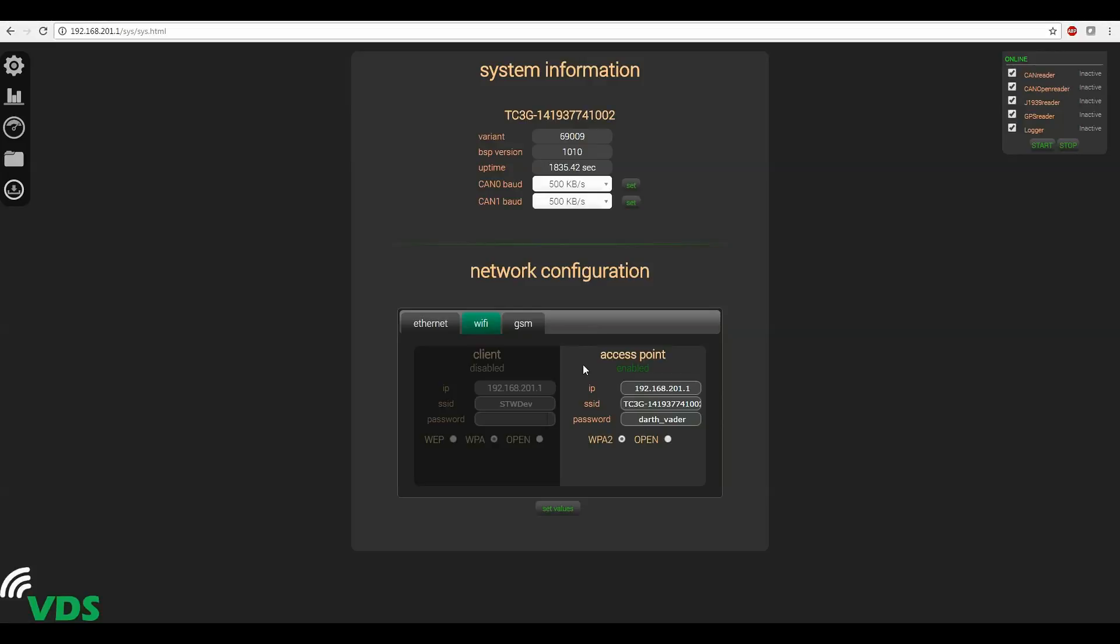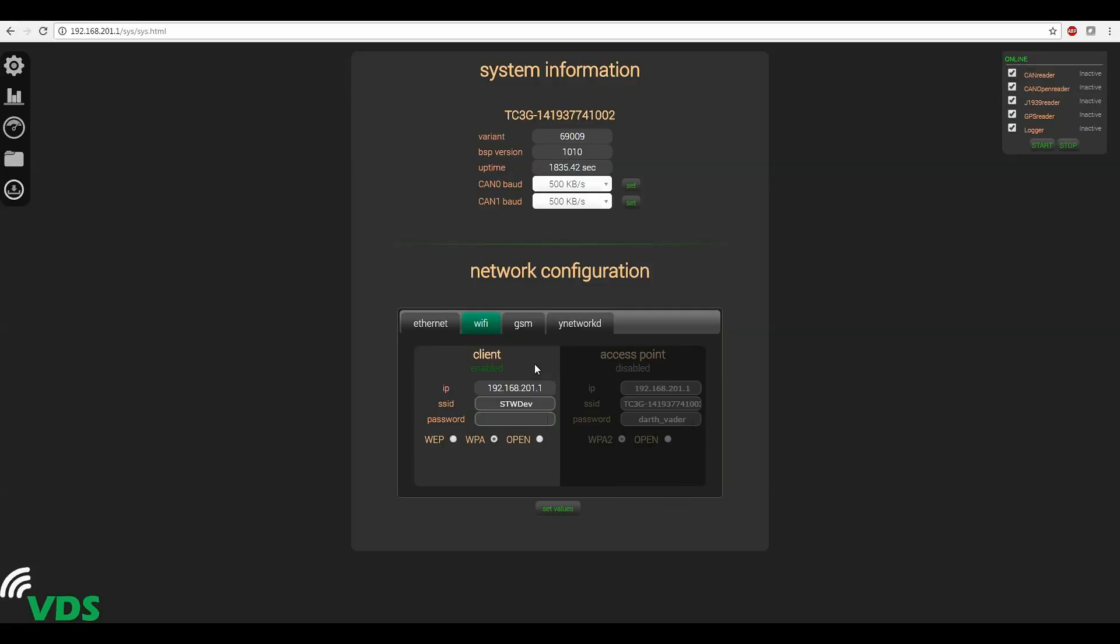Now notice that there's a client option. This is a setting that will allow the TC3 to connect to an existing network. To enable client mode click the box on the left. You'll see the current IP address of the device and then there are fields for the network name and password of the network you want to connect to. Now once you set these two parameters for the network that you're going to connect to click set values to save those changes.